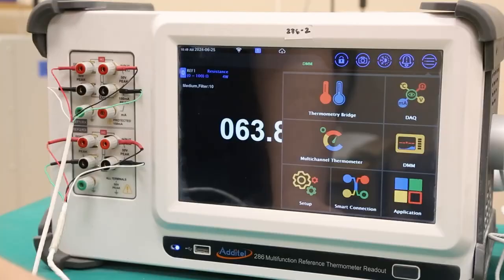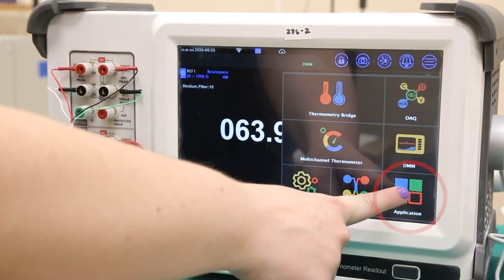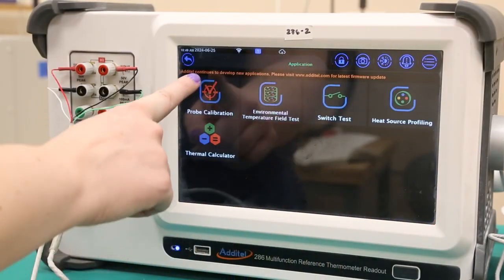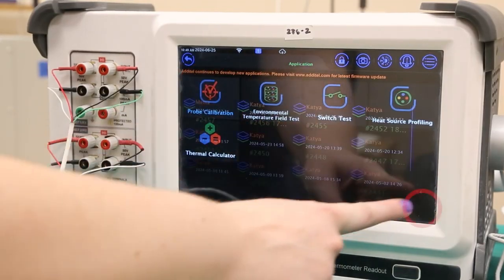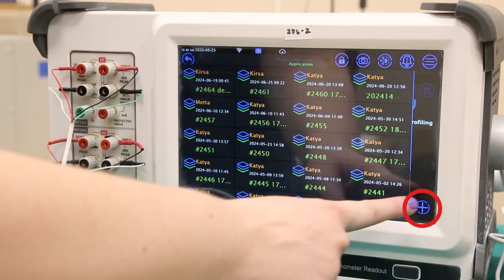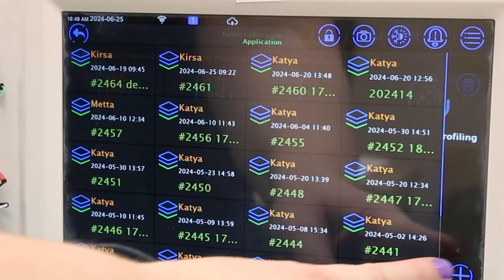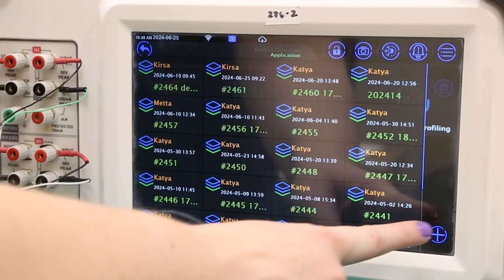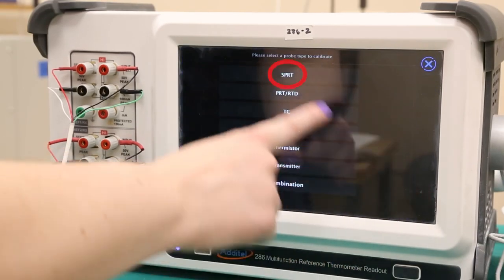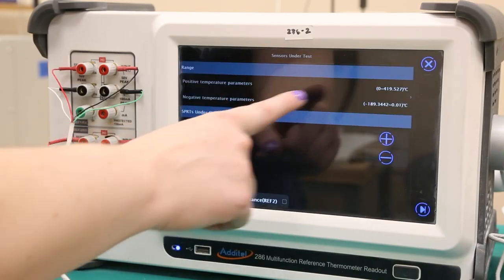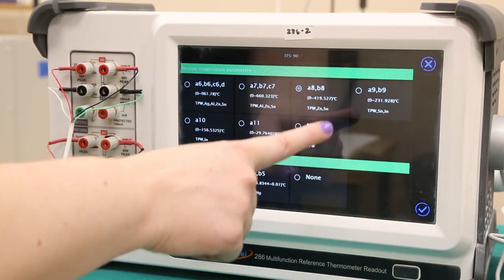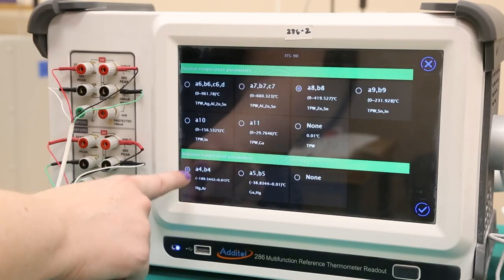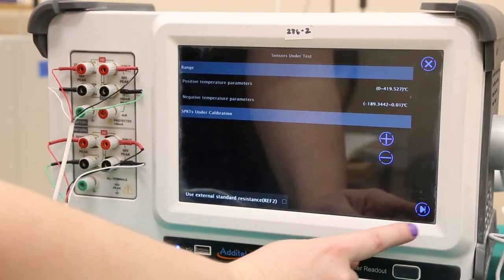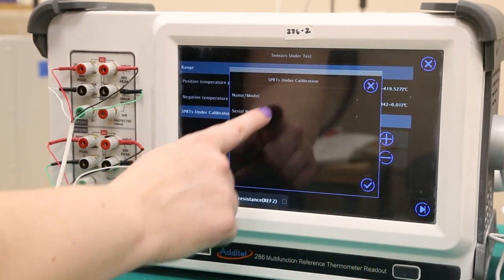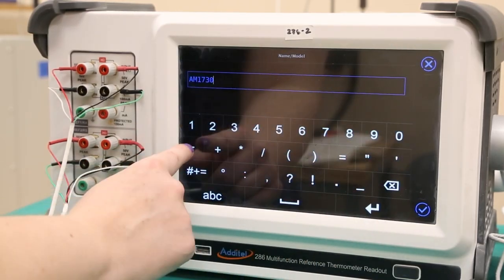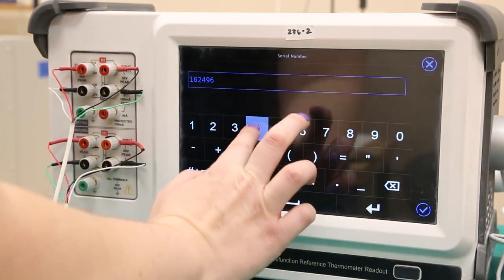Now to set up the calibration test. From the 286 menu screen, select the Application button, then Probe Calibration. Select the plus icon in the bottom right corner to add a new test. These tests are saved to the device and can be revisited at any point in the future. Select the probe type, in this case SPRT. Here we can choose the ITS-90 subranges we will be calibrating, which are 8 and 4 as mentioned previously. Next, we will add the 5 SPRTs that we will be calibrating by pressing the plus button. The name and serial number on these probes should be recorded to ensure accurate traceability.